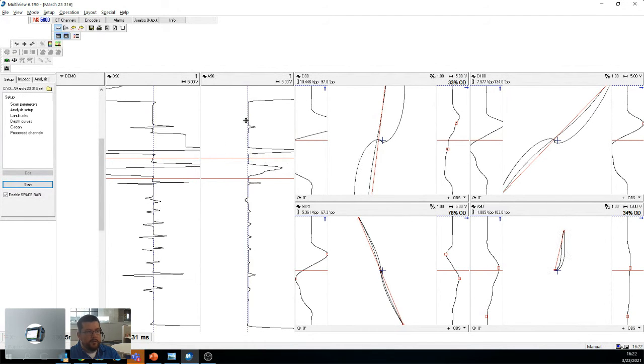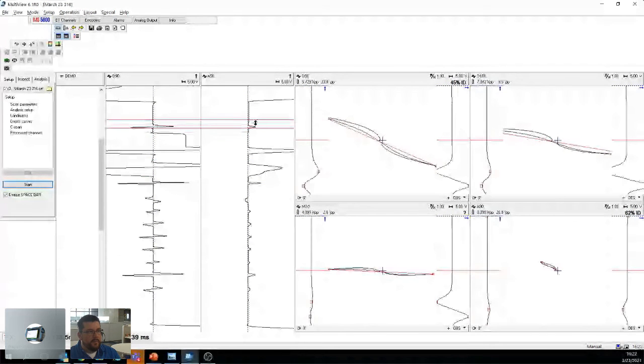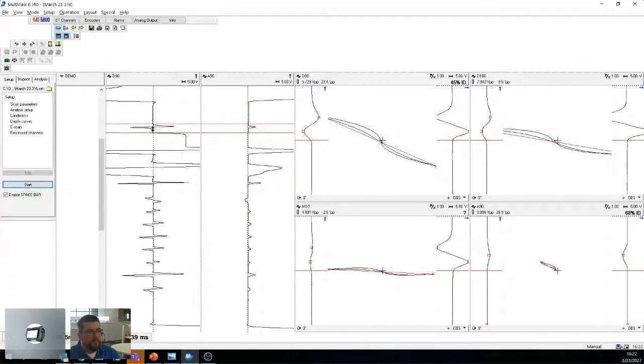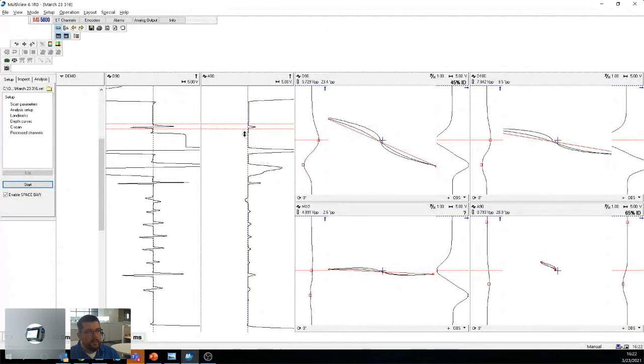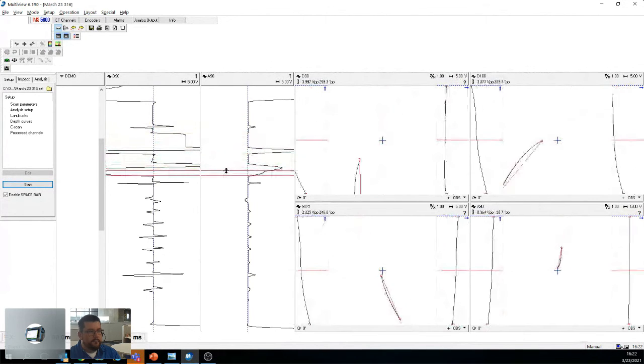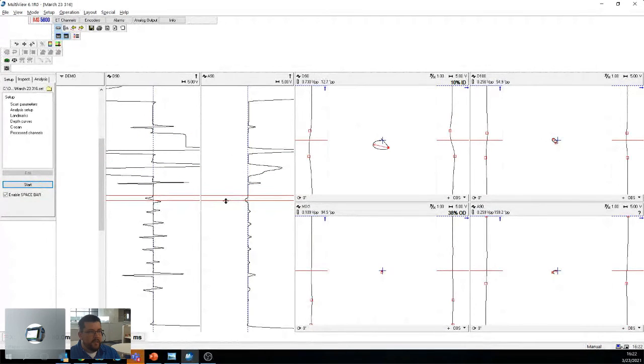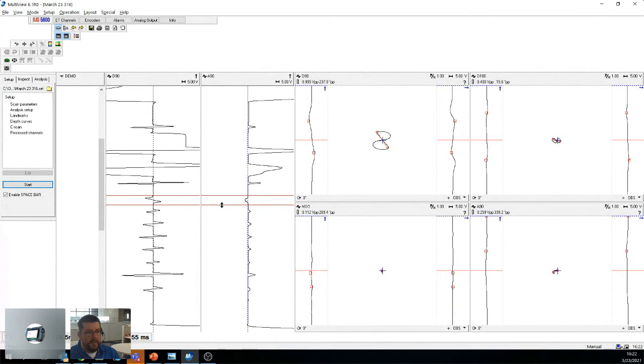Here on the differential, they're super easy to spot, really easy to see. You can almost measure the length if you wanted to. If you had landmarks, you could almost measure exactly how long it would be. It'd be the minus 6 dB anyway, because there is eddy current spread, but you can get a good idea of what's going on here. And once again, your supports are negative.